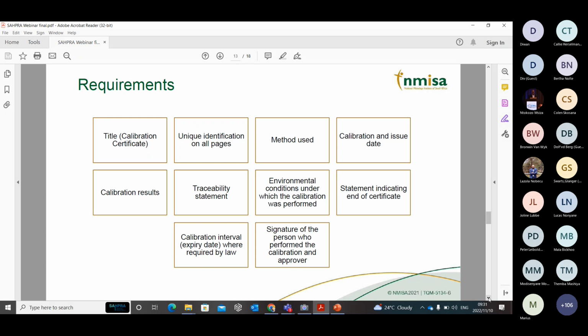There should also be a calibration interval only when that is required by law. If that is not required by law, as a calibration lab, I am not supposed to stipulate the calibration interval for the customer. I can only put the calibration interval upon request by the customer or whenever there are regulations around it, which in our case are stipulated by the regulator, SAHPRA. There should also be signatures of the person who performed the calibration and the approver. In other instances, like NMISA, you will have three signatures: the person who performed the calibration, the checker, as well as the approver.